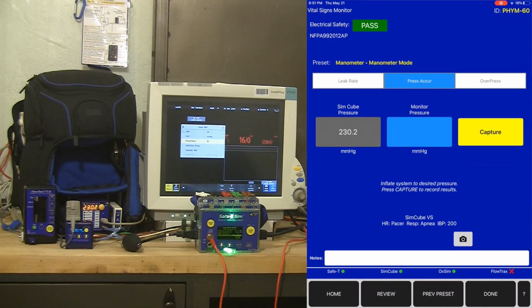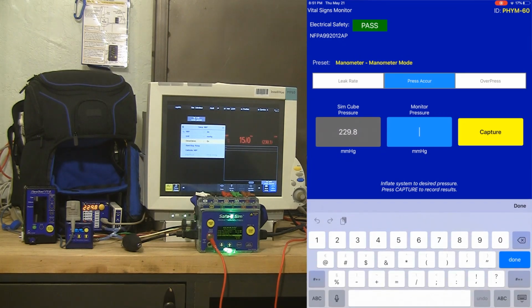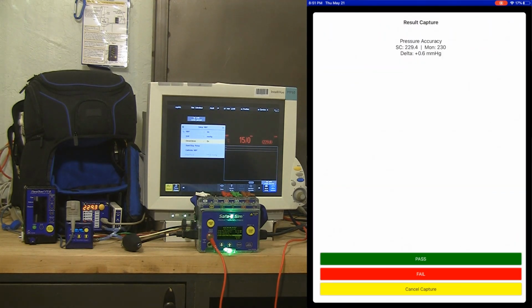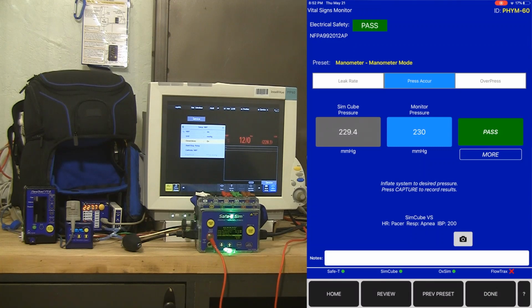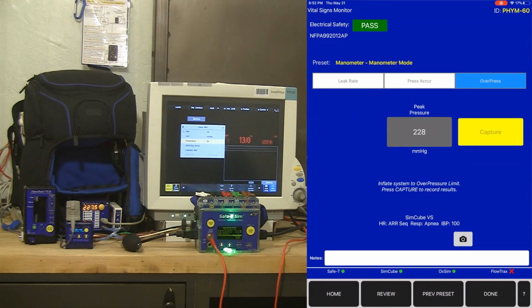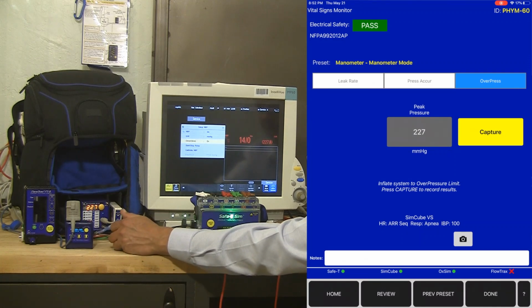I'm going to leave the system inflated at 230 millimeters of mercury or so, and I'm going to type in the pressure seen by the vital signs monitor and hit capture. Now I've got a pressure accuracy result based on the sim cube manometer and the transducer in the NIBP circuit. On the capture screen, we're actually showing the delta as well as both the sim cube pressure and the monitor pressure. So we can see a delta of 0.6 millimeters of mercury, so those two transducers are very close, and we got a pass.